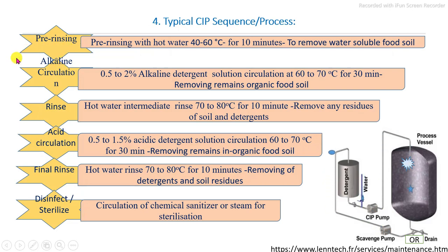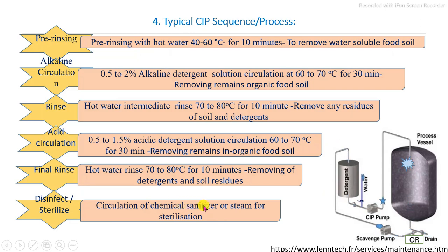These are the main five stages in which complete cleaning is carried out. After that, the final stage is the disinfection or sterilization process, in which chemical sanitizers such as hypochlorite solution or iodine-based solution are circulated, or superheated or saturated steam is used for complete sterilization of the processing line.